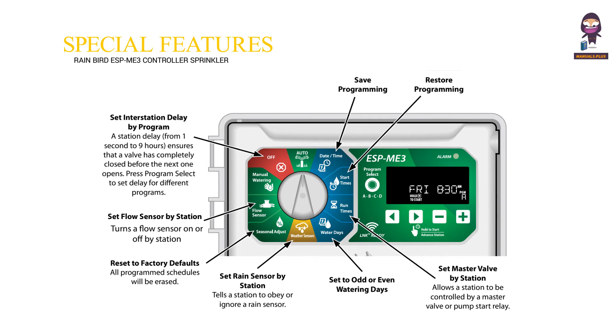Special features. Set interstation delay by program — station delay from 1 second to 9 hours ensures that a valve has completely closed before the next one opens. Press program select to set the delay for different programs. Set flow sensor by station: turns a flow sensor on or off by station. Reset to factory defaults — all program schedules will be erased. Set rain sensor by station: tells a station to obey or ignore a rain sensor. Set to odd or even watering days. Set master valve by station: allows a station to be controlled by a master valve or pump start relay.